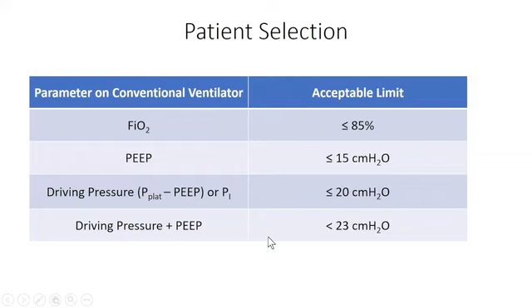particularly an FiO2 less than 85%, and with these other parameters, to be able to deliver the necessary pressure: a PEEP less than 15, a driving pressure, being the plateau pressure minus the PEEP if you're on volume control mode, or the inspiratory pressure on the pressure control mode, should be less than 20. However, the sum of these two has to be less than 23. Again, our machine cannot increase the airway pressure to above 25.